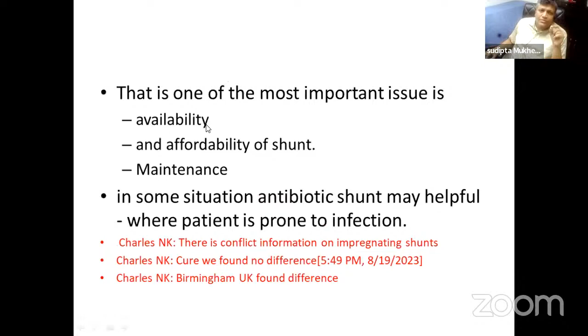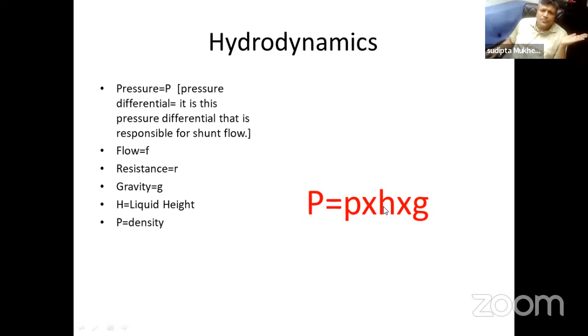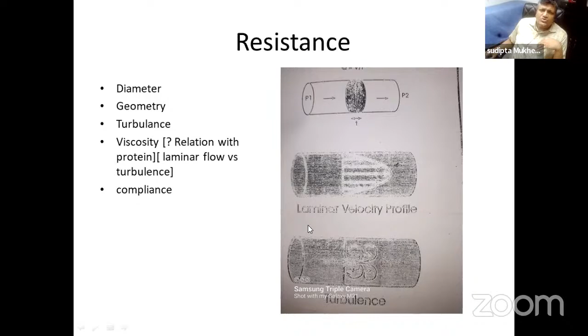Now comes hydrodynamics. How does a shunt work? There is a pressure difference. Pressure difference is related to the density of fluid, that means the density of CSF, liquid height, that means whether the patient is supine or lying down, and gravity and resistance. Resistance is related to the diameter of the tube, geometry, that means whether the tube is curved or straight, turbulence, that is laminar flow or turbulent flow, viscosity of fluid, if high protein is present the viscosity will rise, and compliance of the shunt. So resistance is related to some factors.